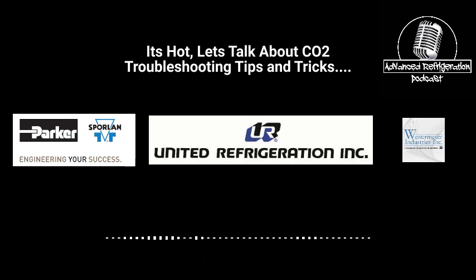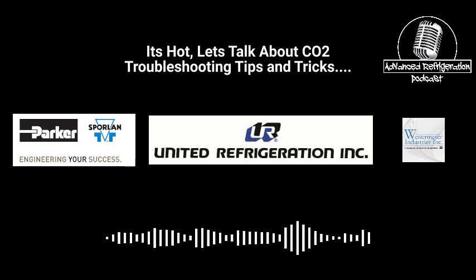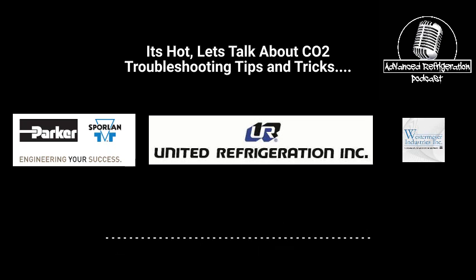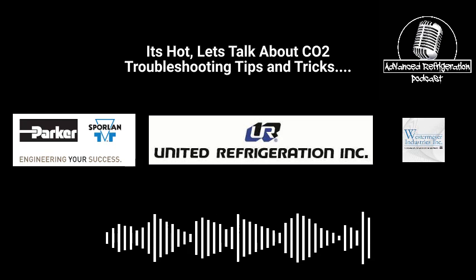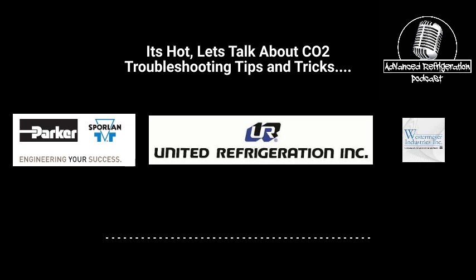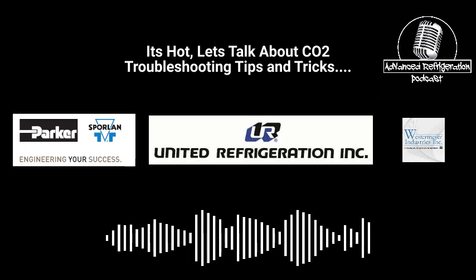Yeah. Anyway, some other high pressure issues. How about blow by on the compressor? If it's blowing by where it's not affecting the high limit and just keeps adding load. We've seen it before where it'll max out the medium temp suction. And if it's that hot out, if it's in the 90s, your gas cooler probably can't handle it. That's another thing to watch out for. Make sure the hot gas injection valve isn't stuck.